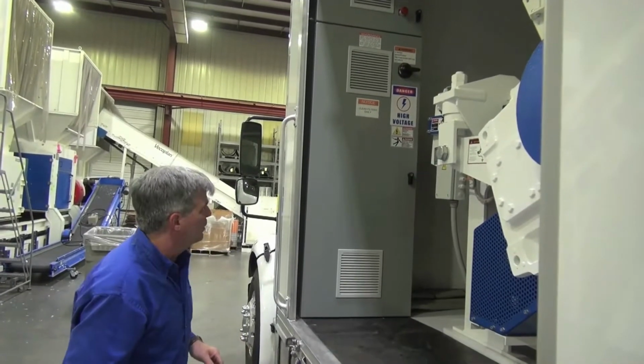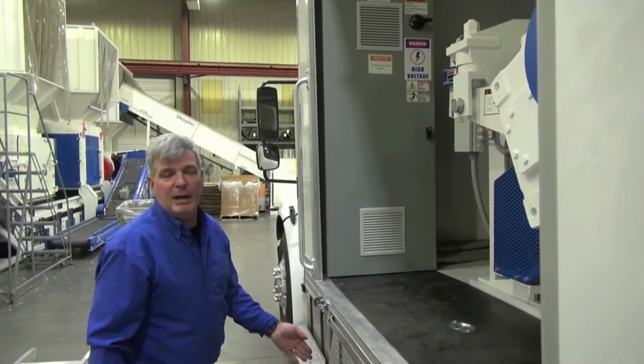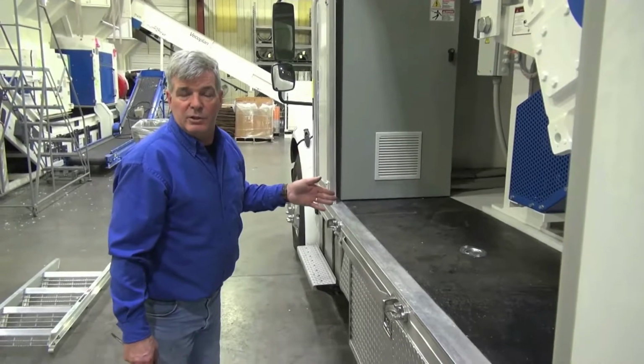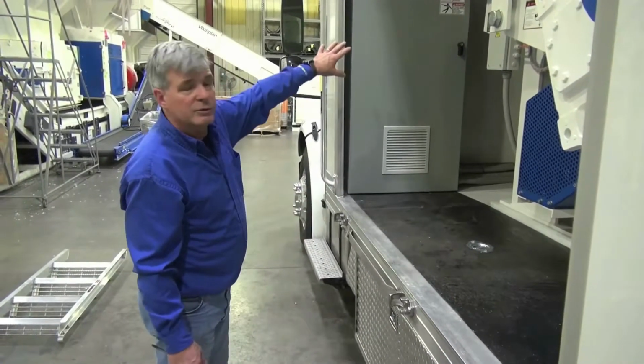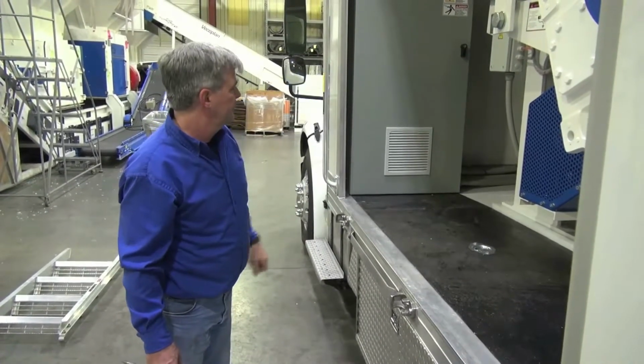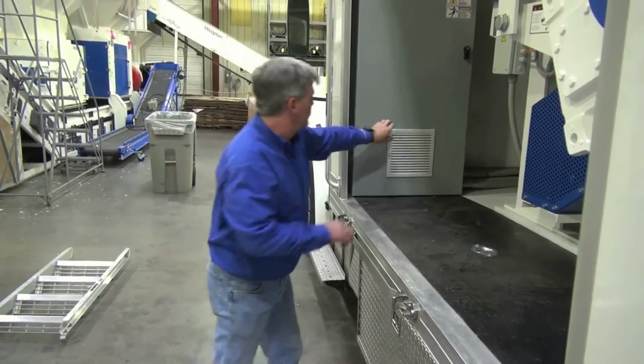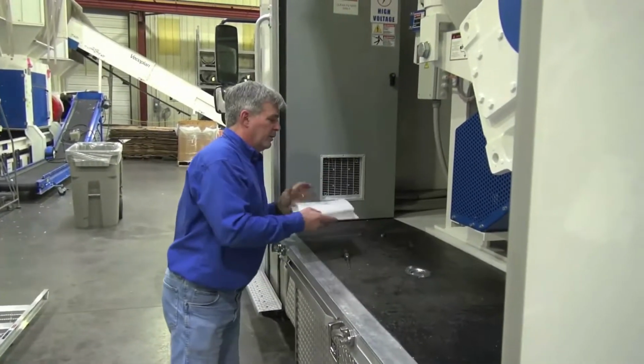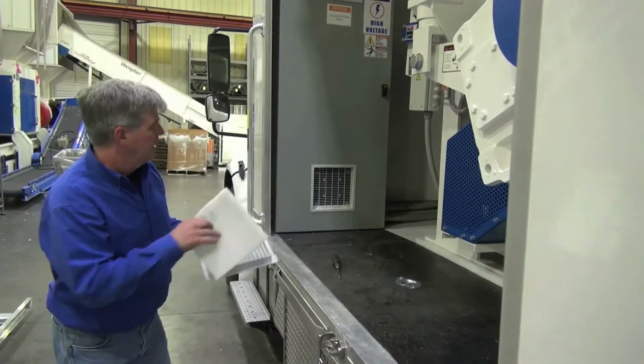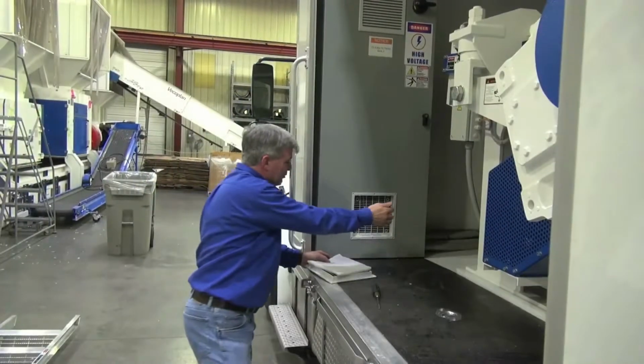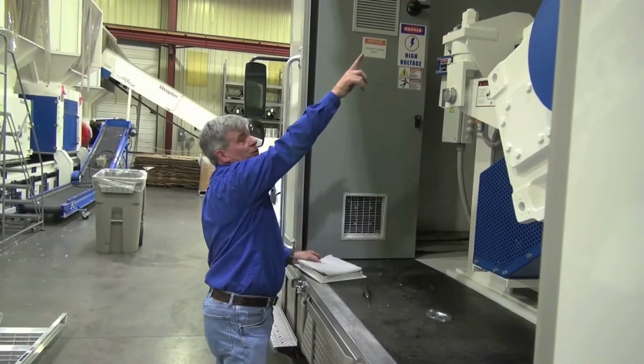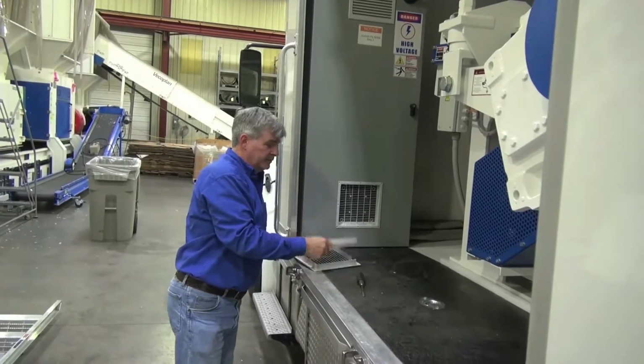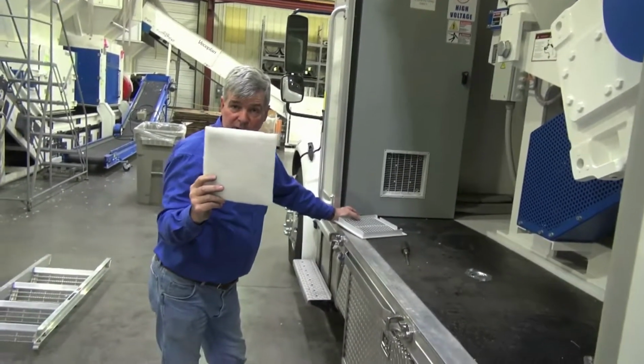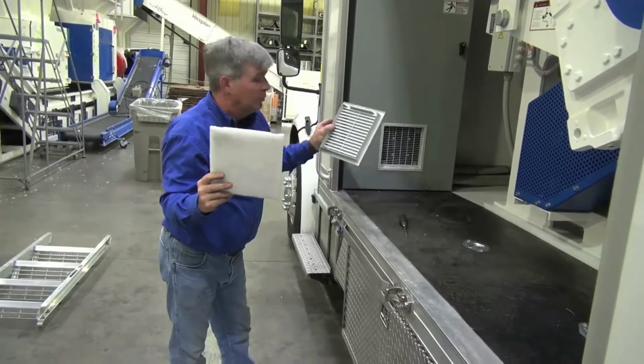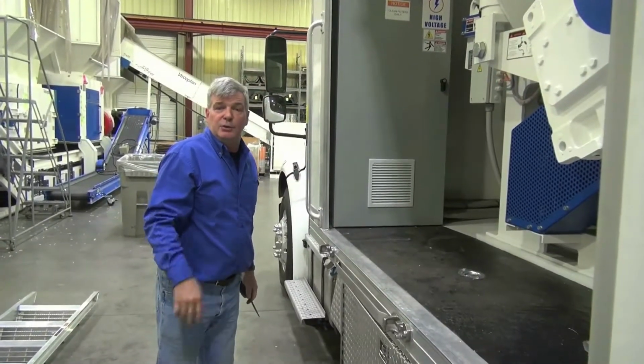It is very important that all plant power or diesel engine are shut down when someone is in this control panel. There are filters in these control panels. One in the bottom, one in the top. Air is drawn in the bottom and out the top of the panel to help cool the panel. The filter on the inside of this grate will keep the dirt out of the panel. It's recommended that these filters are cleaned daily.